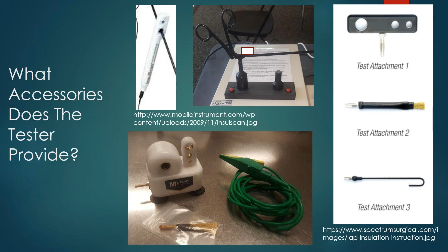How are accessories replaced? Let's say you do find damage. How do you replace them? Are they free? Do they get repaired? Or is there a cost associated with that with your vendor? Now, another question to ask is, will education in-service be provided by the vendor? Are the IFUs accessible? What if they're lost? Are they available online, on a CD, on paper, or all three? So again, education is essential because you want to make sure you're using the equipment according to the IFU, as well as how to use the accessories.